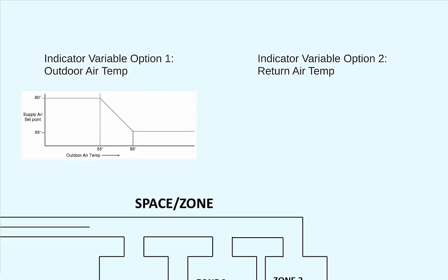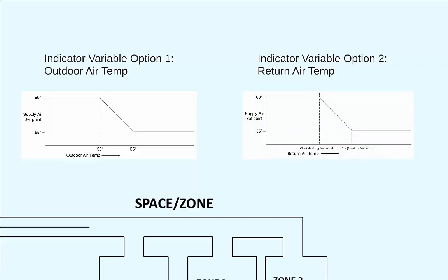Thus, when anything less than the cooling set point of 74 is sensed in the return duct, this would be a good time to start increasing the supply air temperature. So a supply air temperature reset schedule following this approach may look something like this. If the return air temperature gets to the point where it is reading 71 degrees Fahrenheit, which again was our heating set point, that would be an indication that most of the building is in heating mode.